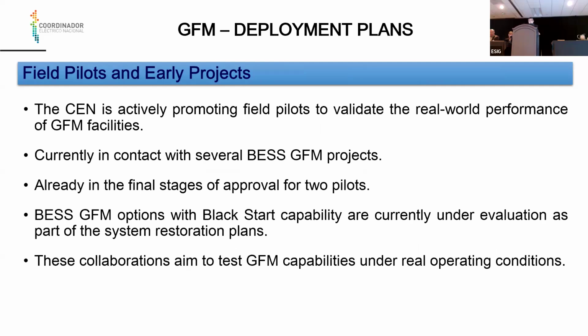Another important project, which is very advanced in its development, is actively promoting field pilots to validate the real world performance of grid forming in our system. We are currently in contact with several grid forming BESS projects. Already, we are in the final stages of approval for 2 pilots, 2 big BESS projects of more than 200 and 400 megawatts. We are working on black start capability too, because the blackout revealed some opportunities to improve our system restoration plans. So we saw grid forming as an ideal solution.